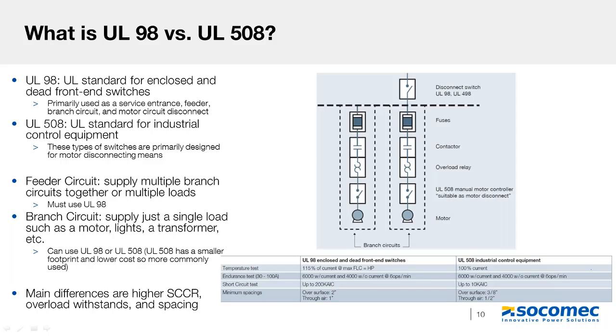And then the UL508, which are switches for motor disconnecting means, these are used just for motor applications. If you use one of these for a feeder circuit, it's a misapplication. And I know that the size and cost difference of a UL508 switch makes it really tempting to use, but the liability concerns of using a UL508 switch in a UL98 application are very high. So you need to be very careful that you're using the right switch for the right application.